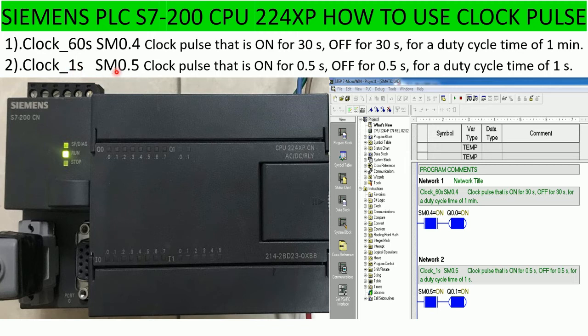And if we use SM0.5 clock pulse memory, it will turn on 0.5 second and turn off 0.5 second also, on a cycle time of 1 second. So it is very fast if we use SM0.5. It will turn on and off within 0.5 second on a cycle time of 1 second.